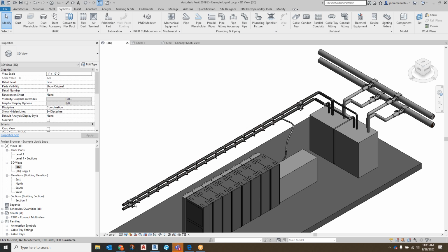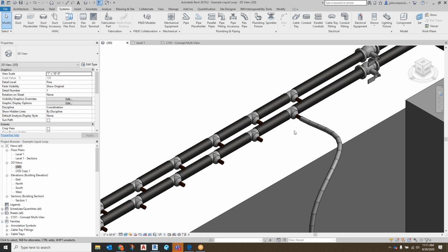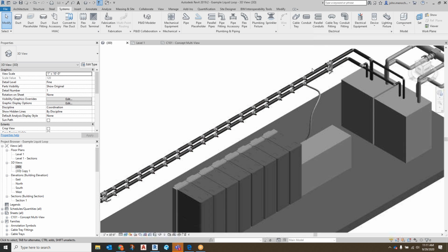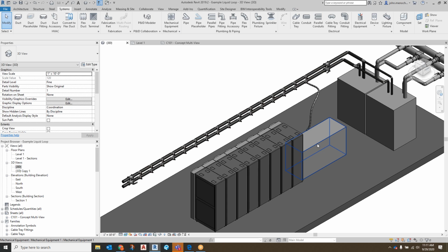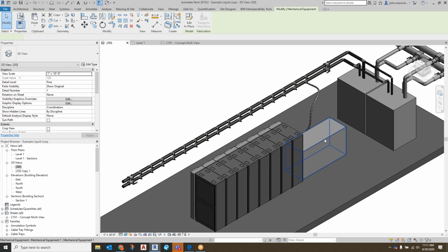These CDUs I drew based on a design I've used that has internal valving over here. Otherwise, I'd want valving on here to be able to remove this for maintenance. So it's likely they'll encounter stub-offs on an existing loop of chilled or cooling water that are larger or smaller than needed, and they need to know what that means. So that's one of the topics.